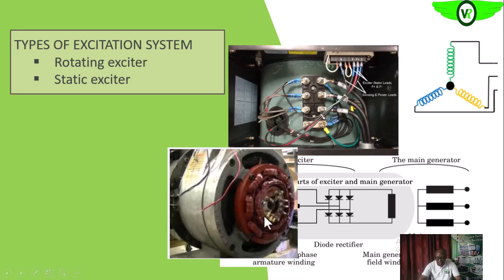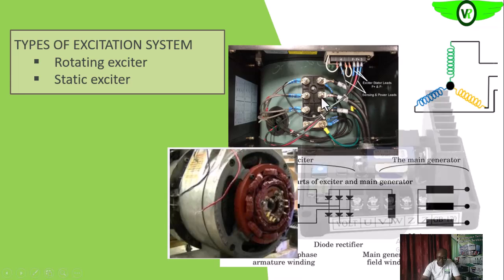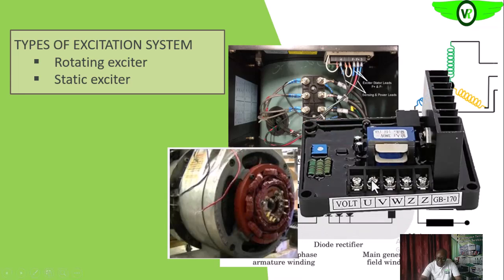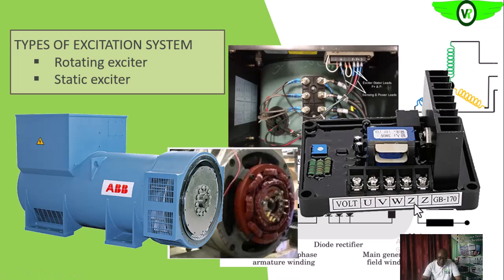This is the exciter armature. You can see the diode plate that does the rectification of what comes out of the armature before it is sent into the field. Then these two wires, red and black, are what will now be fed by the AVR. Remember, the AVR gets its input from the output of the main generator. So this is the AVR for the three-phase inputs U, V, W. Then this is the plus and minus to the exciter feed.